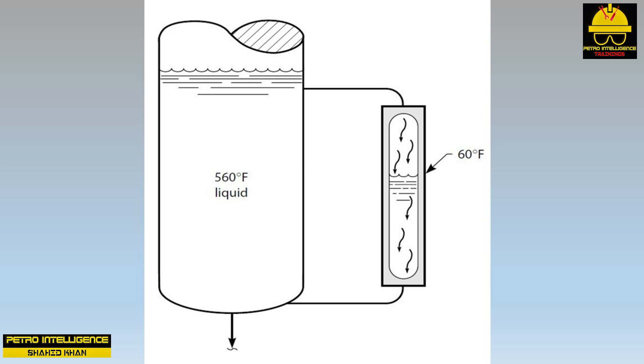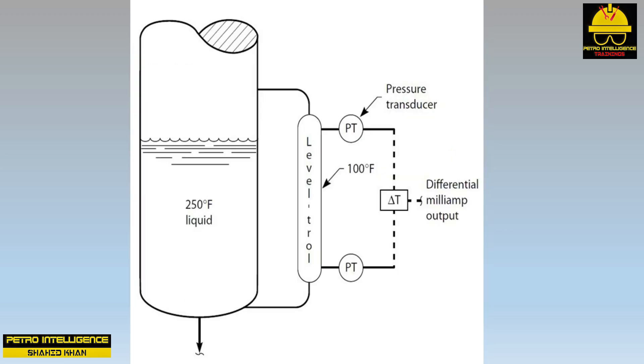As the liquid level in the tower increases beyond five feet, the indicated liquid level would remain at 92%. Once the actual liquid level inside the tower bottom rises above the top level tap, no further increase can be observed in the gauge glass — we say the level indication is 'tapped out.' The same problem arises in a Level-trol, which measures and transmits process vessel liquid level to the control center using two pressure transducers that convert a pressure signal into a small electric current.